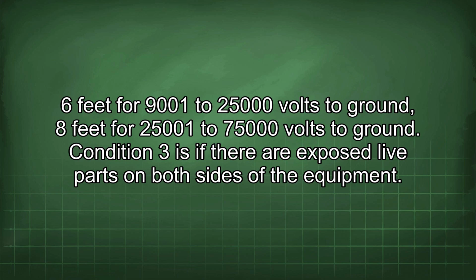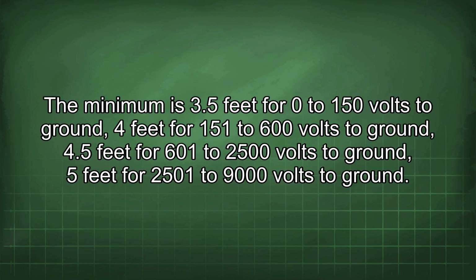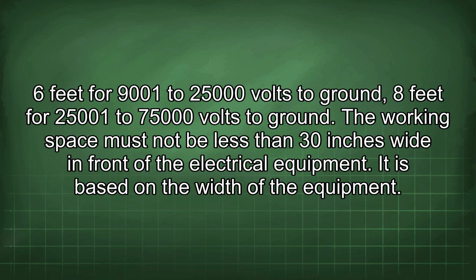Condition 3 is if there are exposed live parts on both sides of the equipment. The minimum is 3.5 feet for 0 to 150 volts to ground, 4 feet for 151 to 600 volts to ground, 4.5 feet for 601 to 2500 volts to ground, 5 feet for 2501 to 9000 volts to ground, 6 feet for 9001 to 25,000 volts to ground, 8 feet for 25,001 to 75,000 volts to ground.